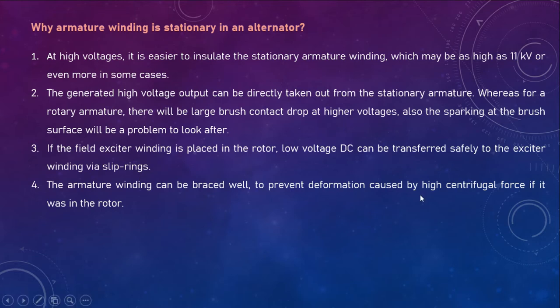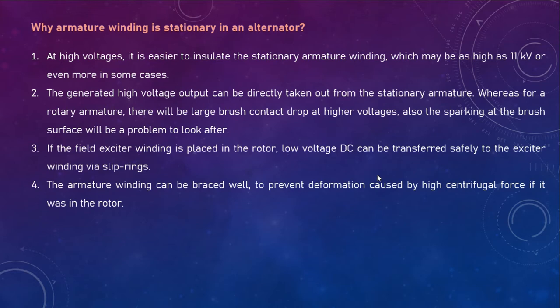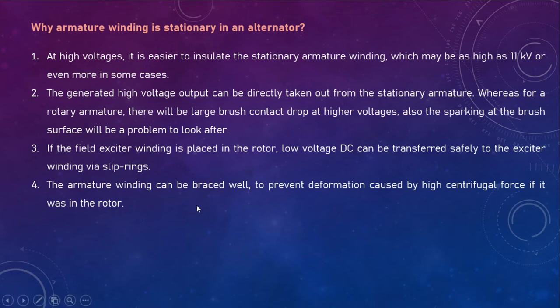The armature winding can be braced well to prevent deformation caused by high centrifugal force. If the armature winding were in the rotor, continuously rotating at very high speed to generate very high voltage, deformation caused by centrifugal force could occur. It would have to be braced very tightly in the rotor. This problem can be avoided if it is placed in the stator side. These are the main advantages of stationary armature winding in the stator.